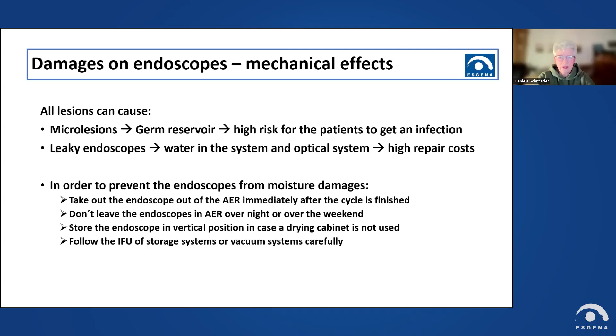Avoid knocking and free dangling. So please, better to fix it also in the drying cabinet. Avoid crushing during all the procedures, reprocessing and treatments. Close the door carefully. Don't insert against resistance. Straighten the endoscope if necessary. Sharp instruments, also for your protection.